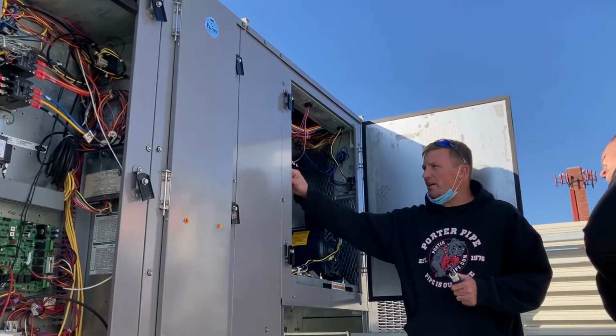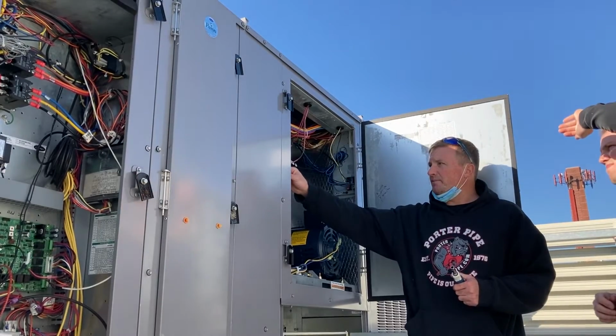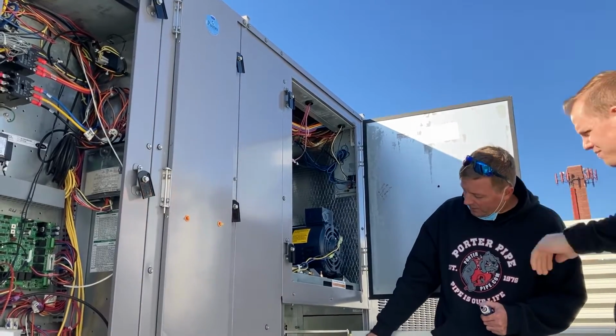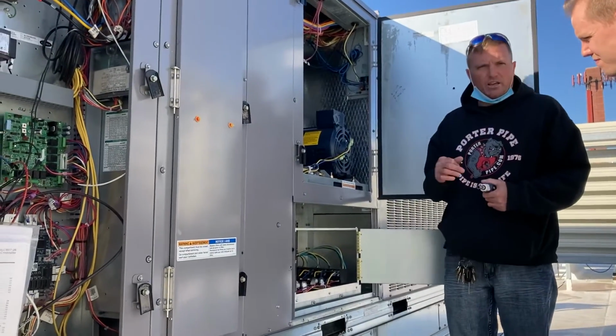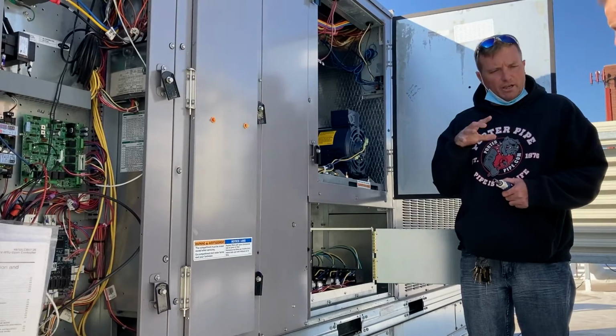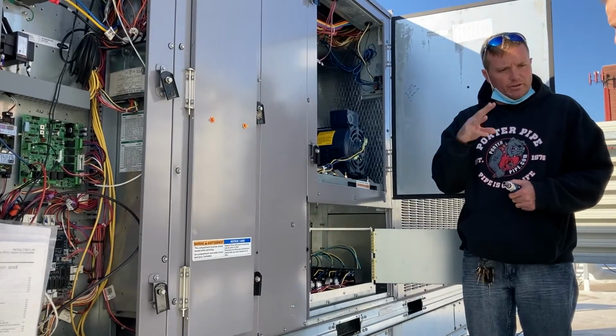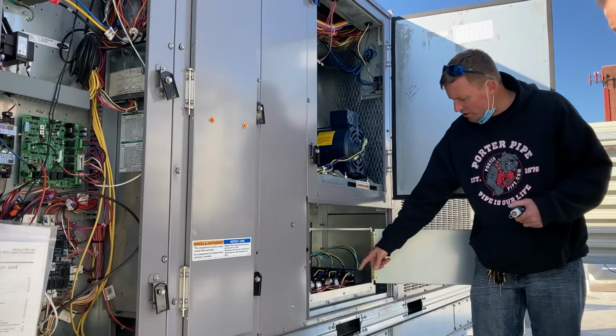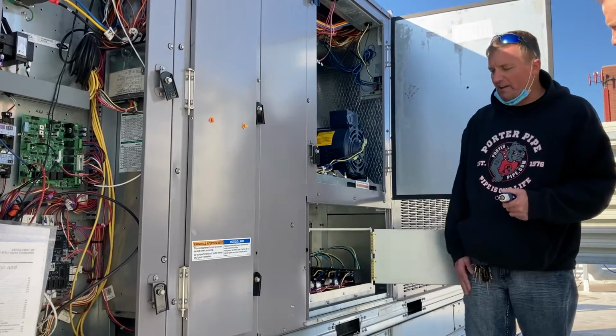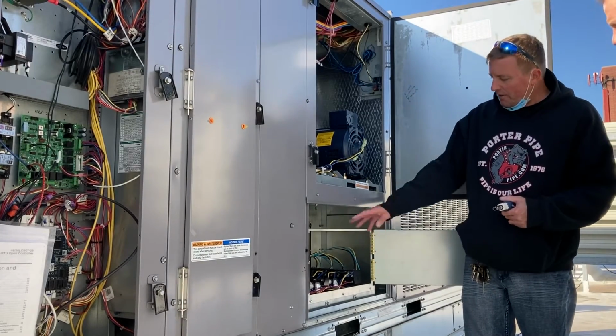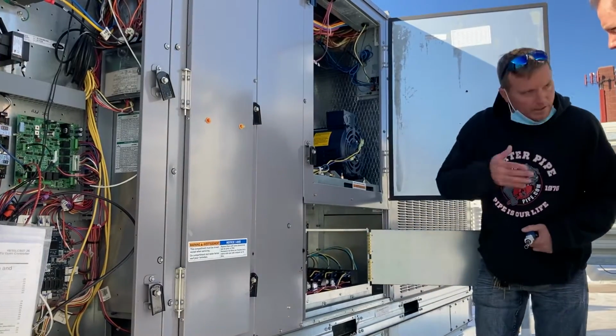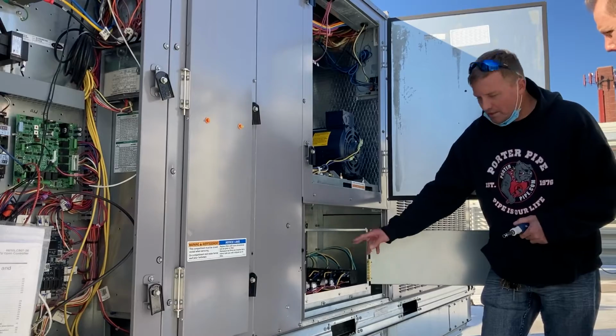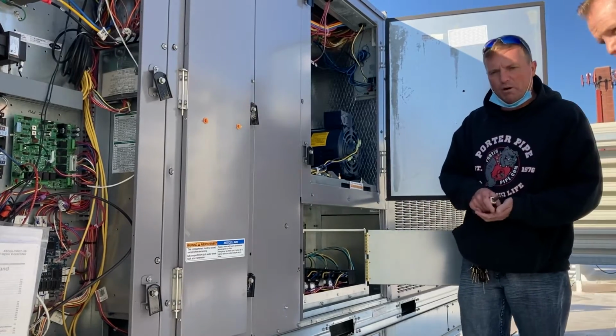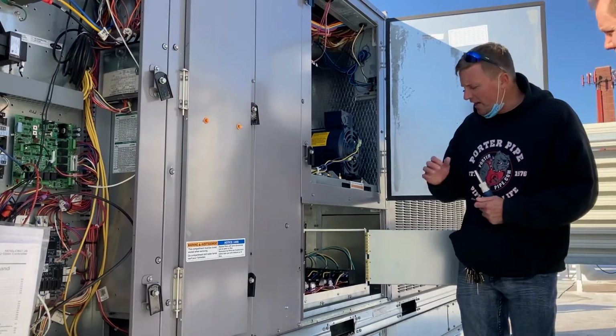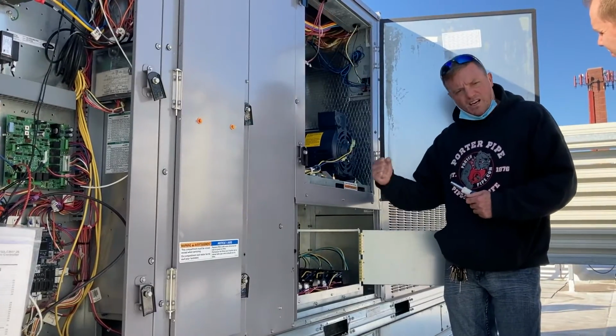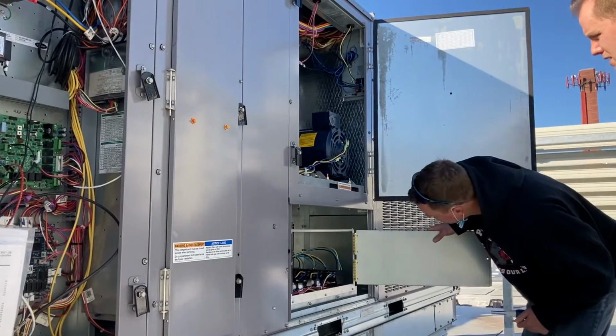Same thing, pressure status here for the prover, okay? Dirty filters. So electric SCRs, those are the relays. With the SCR relay, there's going to be one call for heat. If the temperature doesn't get up fast enough, it'll bring the other one on, it'll stage it. So you don't need to worry about anything else other than your 24 volts coming off of that. That's really it. All fused. If we have anything dead or blown in here, we need to check the windings of the coil, obviously, and go across these to make sure we haven't had any kind of electrical break or a wire bust in any of the electric coil. It's standard. Instead of just bringing it on in one, we'll stage it now. So that's pretty self-explanatory.